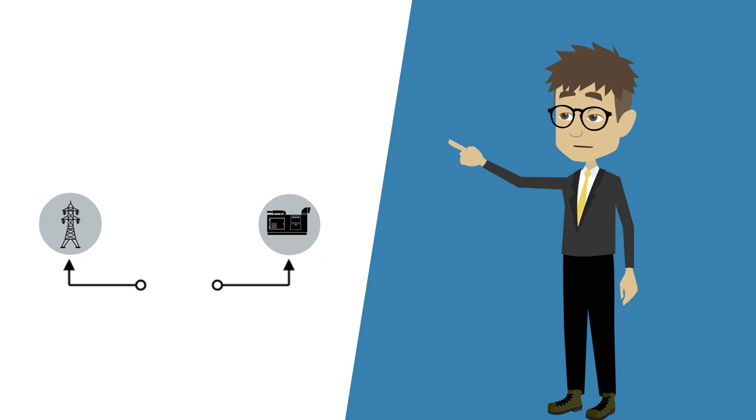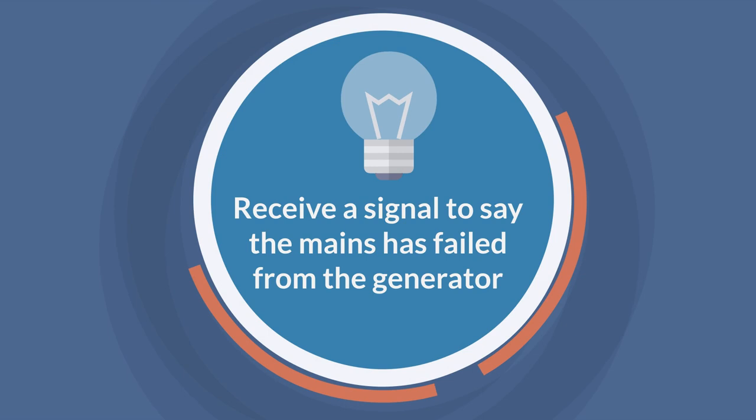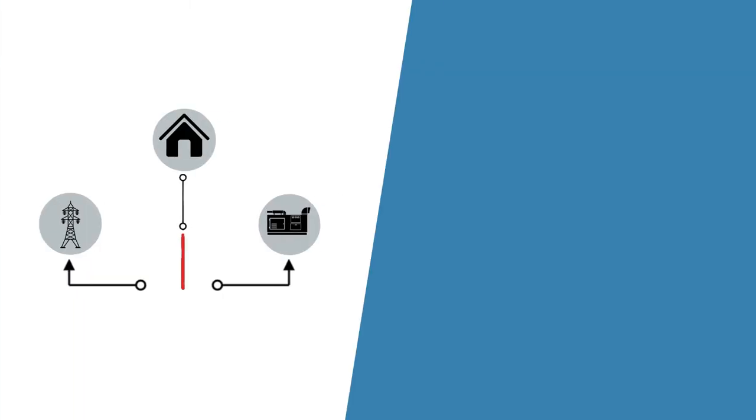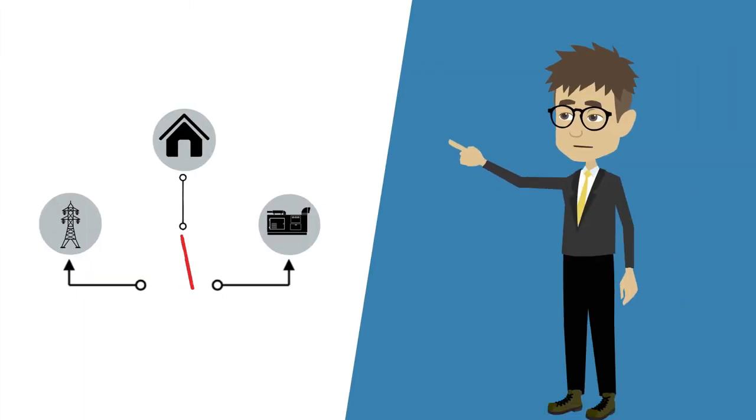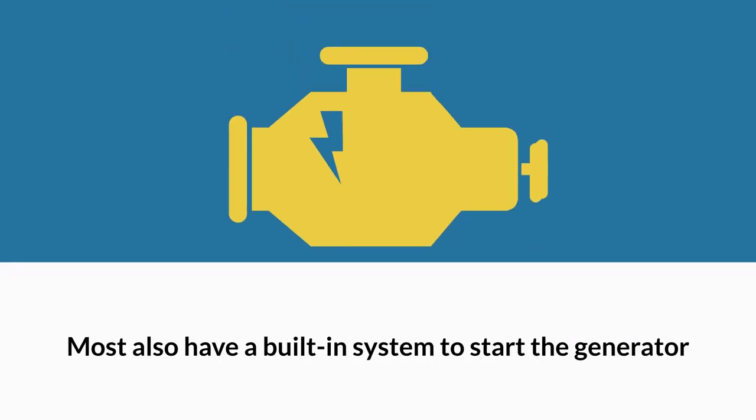Automatic transfer switches either have a method of detecting the mains failure or receive a signal to say the mains has failed from the generator. They then switch between the mains and the generator automatically. Most also have a built-in system to start the generator when the mains electricity fails.